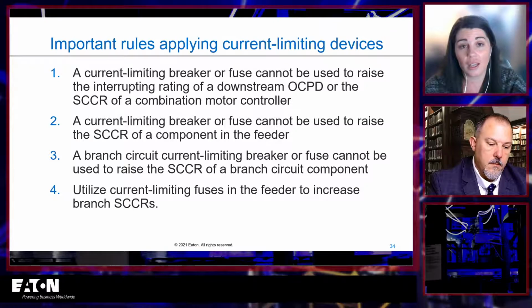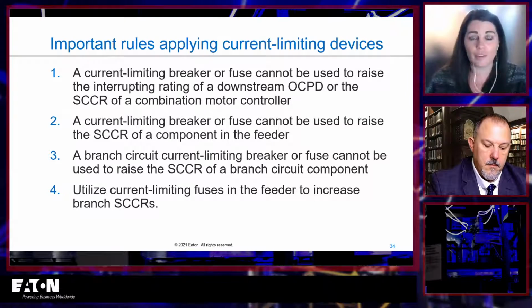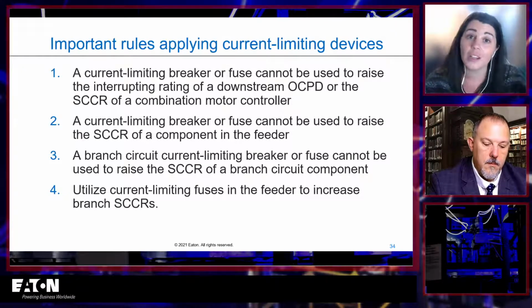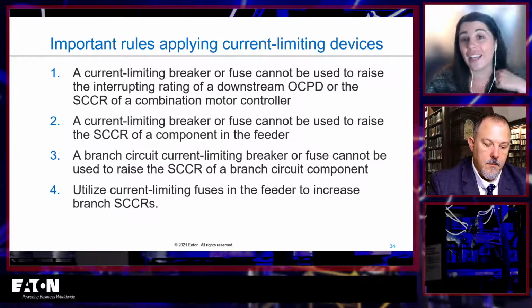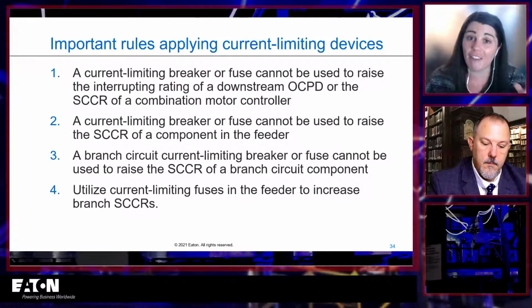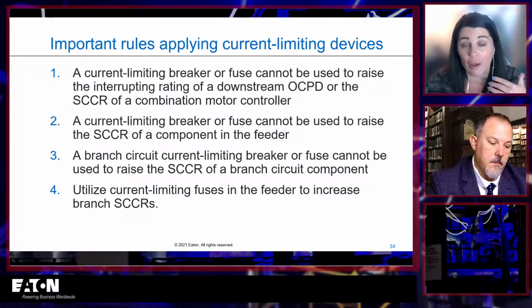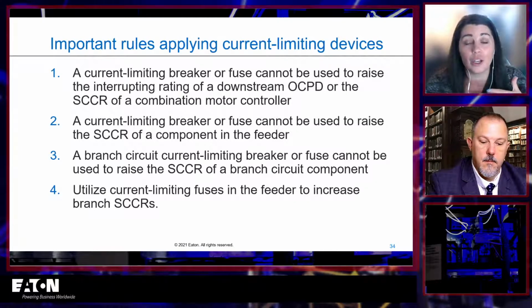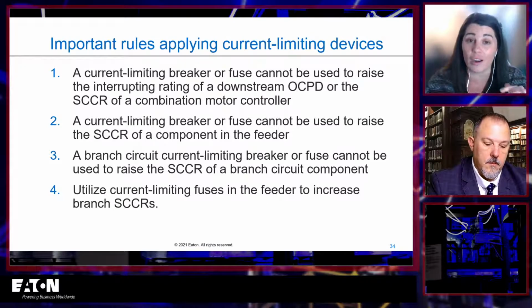So I always like to emphasize this, because a lot of people read that and say, oh, that means if I put a current limiting fuse as my main, I get a really high rated panel. It's not necessarily true, right? You can't use it to raise interrupting rating. So you have to have high interrupting rating overcurrent protective devices all throughout your panel before you can do that. You also can't use it to raise the SCCR of a combination motor controller.